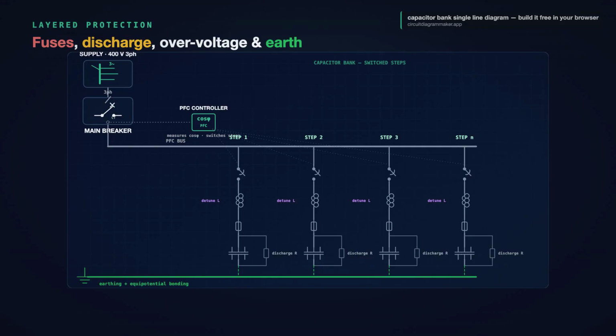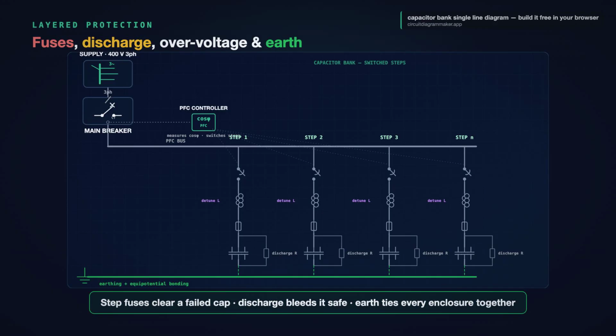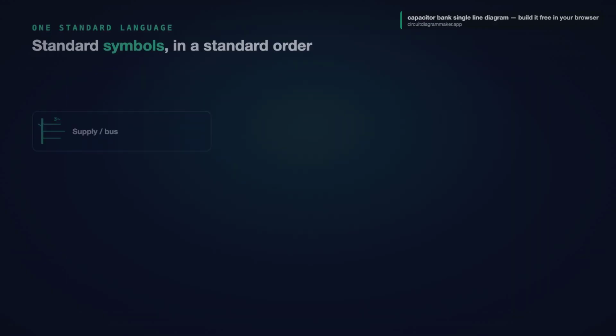Step back and look at the protection, because a capacitor bank has layers of it, and the one line shows everyone. At the top, the main breaker or fuse switch clears a bank-wide fault. On each step, the fuses clear a single failed capacitor. Across each step, the discharge resistor makes the caps safe to touch and safe to reswitch. In series with each step, the detuning reactor keeps harmonics from destroying the caps. The controller itself protects against overcorrection and overvoltage, dropping steps out when it must.